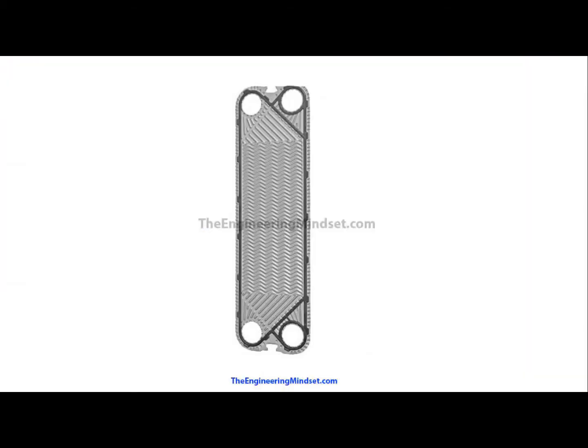Now you can see a real heat exchanger plate on the screen. These are typically made from steel or titanium, with a pattern grooved or stamped into them. These patterns strengthen the plates, which are incredibly thin, and also increase the heat transfer surface area, as well as creating a very turbulent flow inside them. So it's not smooth; all the water has to tumble across these and comes out very rough and turbulent.